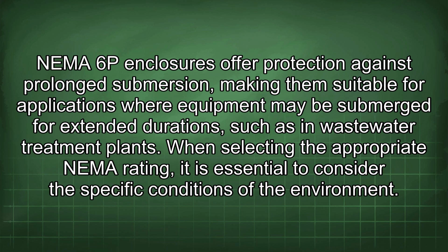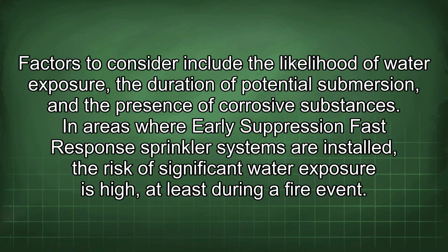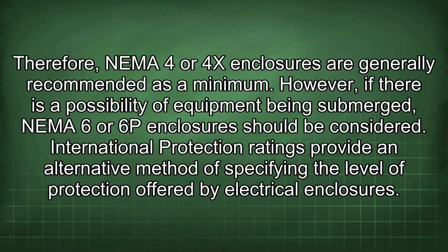When selecting the appropriate NEMA rating, it is essential to consider the specific conditions of the environment. Factors to consider include the likelihood of water exposure, the duration of potential submersion, and the presence of corrosive substances. In areas where early suppression fast response sprinkler systems are installed, the risk of significant water exposure is high, at least during a fire event. Therefore, NEMA 4 or 4X enclosures are generally recommended as a minimum. However, if there is a possibility of equipment being submerged, NEMA 6 or 6P enclosures should be considered.